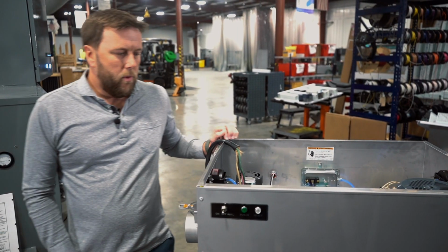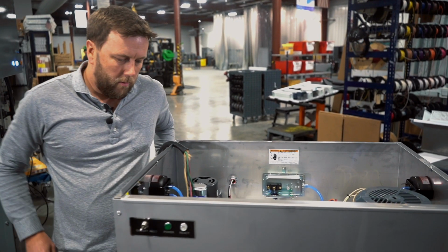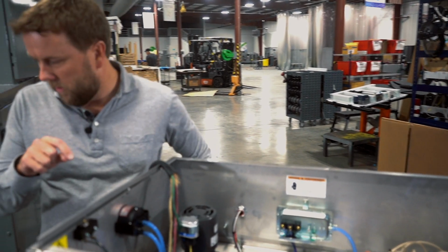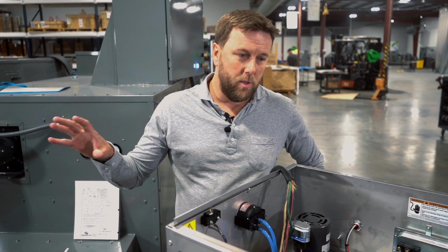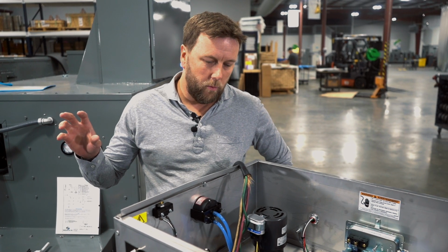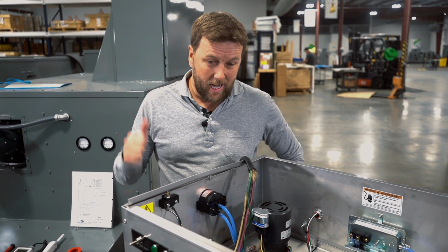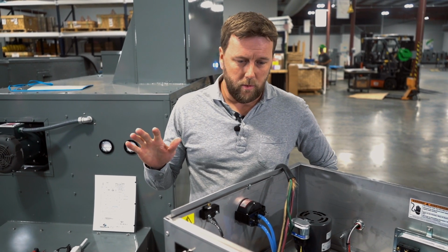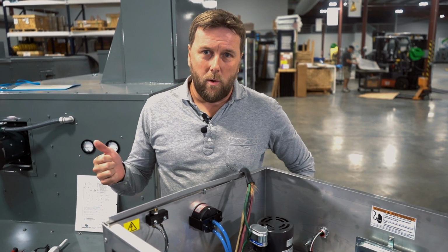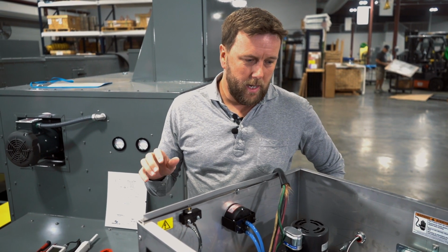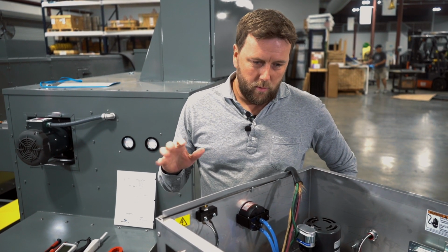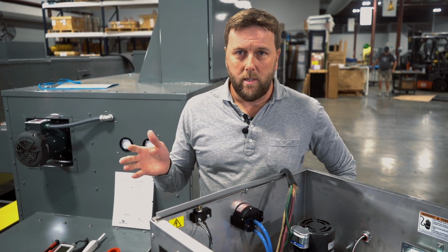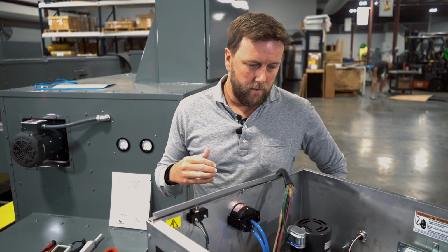So the first thing that we want to make sure that we have is proper power installed to the unit. In this situation, we've got a 480 volt, 3-phase system. That is high voltage, so we absolutely want to respect the power and make sure that we do not make any movements or actions that could put us in danger of being electrocuted.